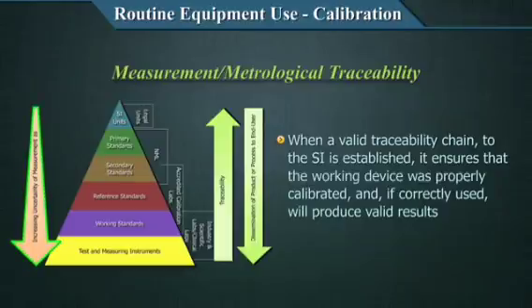If you look at the left side, there's another arrow coming down, and that is your degree of uncertainty. As the dissemination of the standard comes down, the degree of uncertainty increases. If the uncertainty is very small at the initial phase, it increases to a much more substantial degree as it reaches the testing or measuring instruments. However, there are limits to the degree of uncertainty which is acceptable, and that's why the uncertainty must be mentioned on any calibrator, and you can decide if this calibrator is okay for your laboratory.